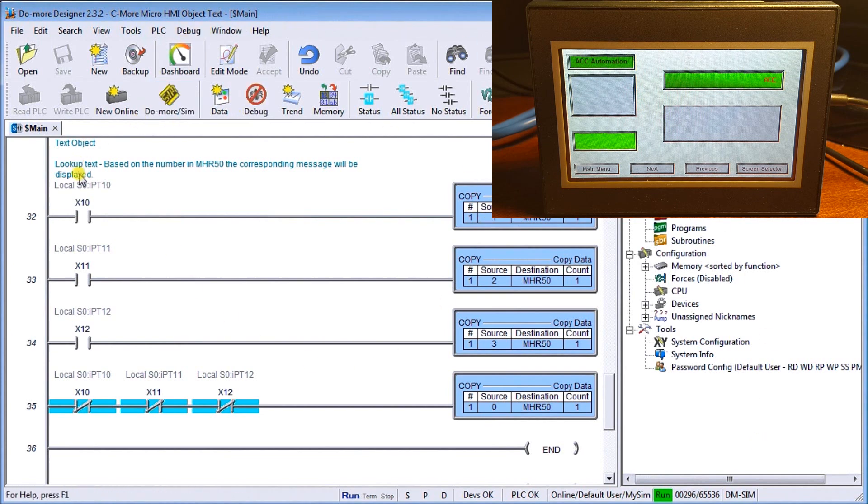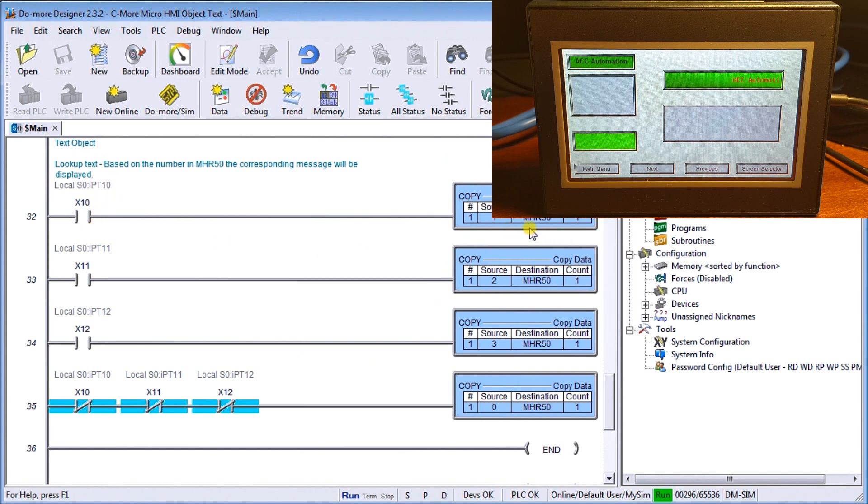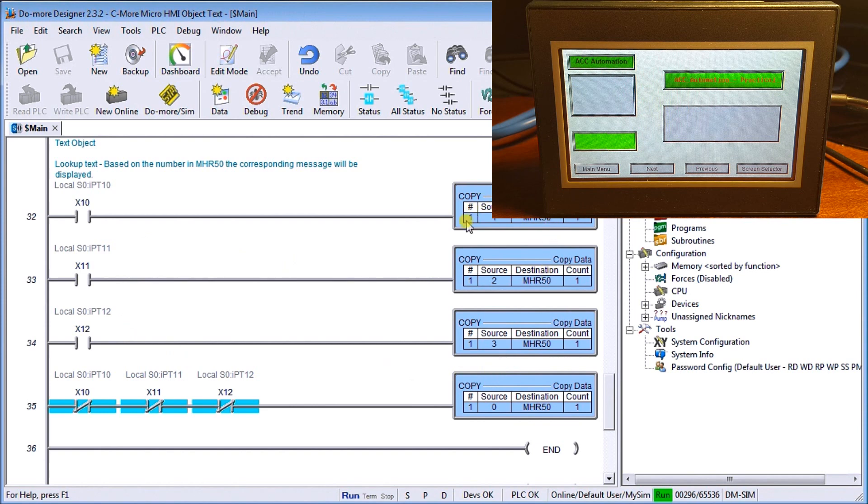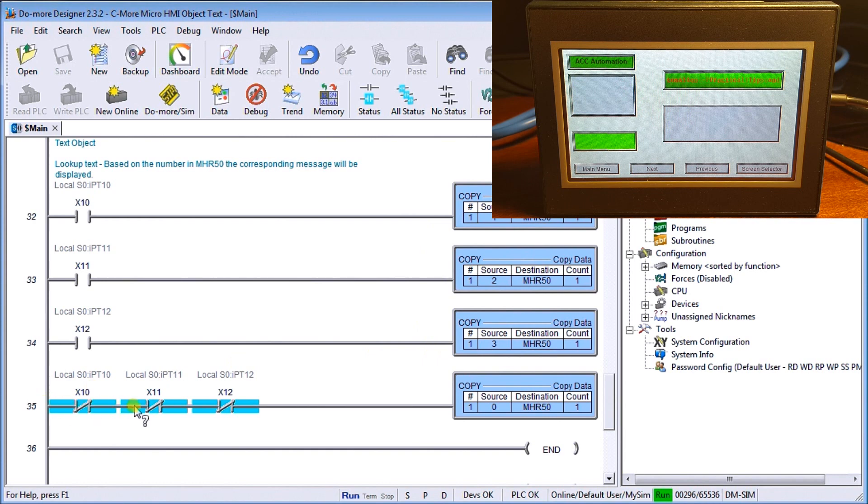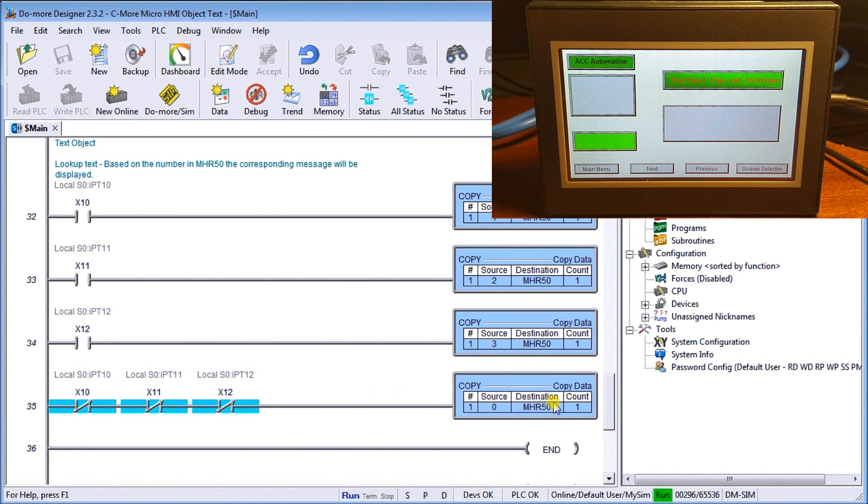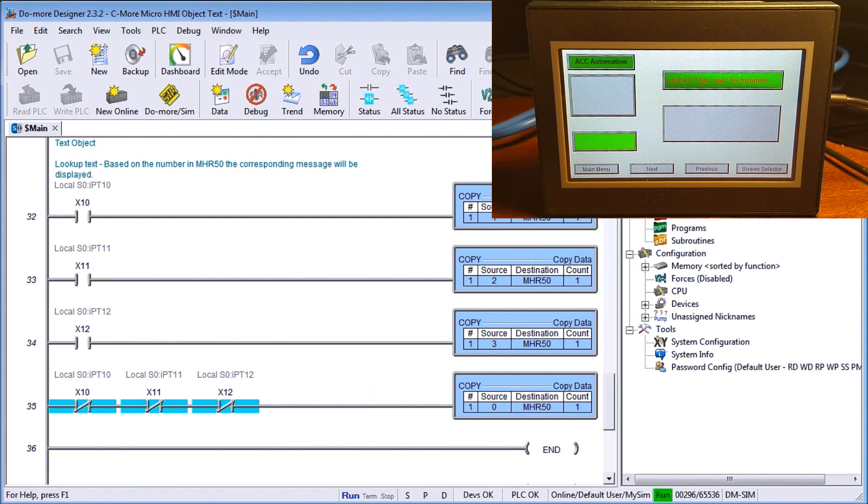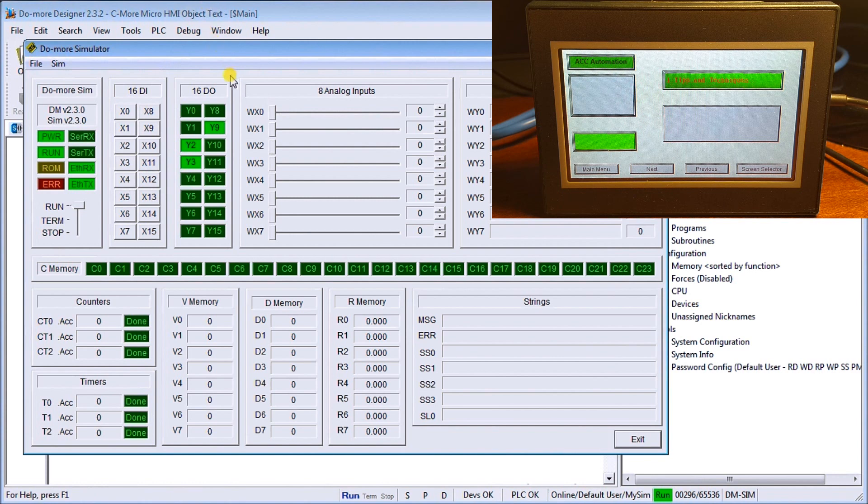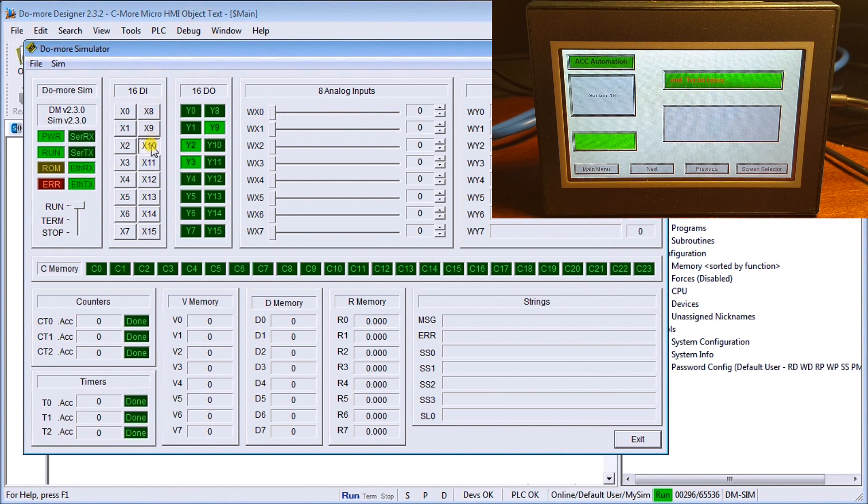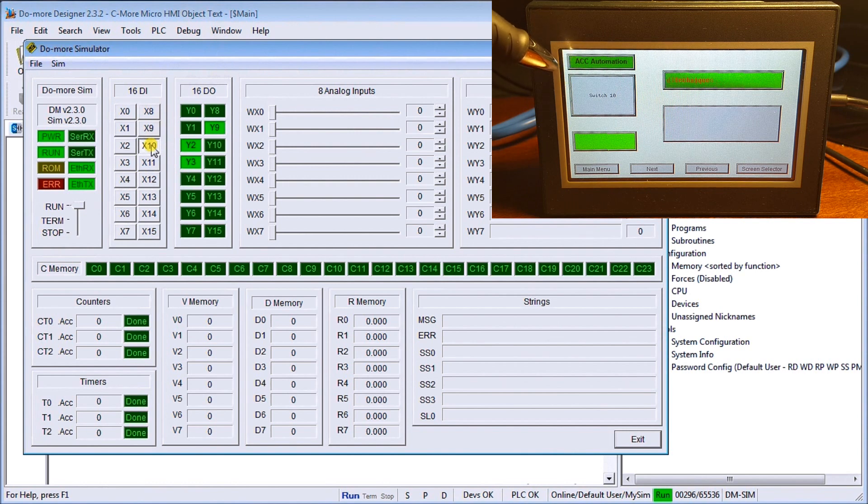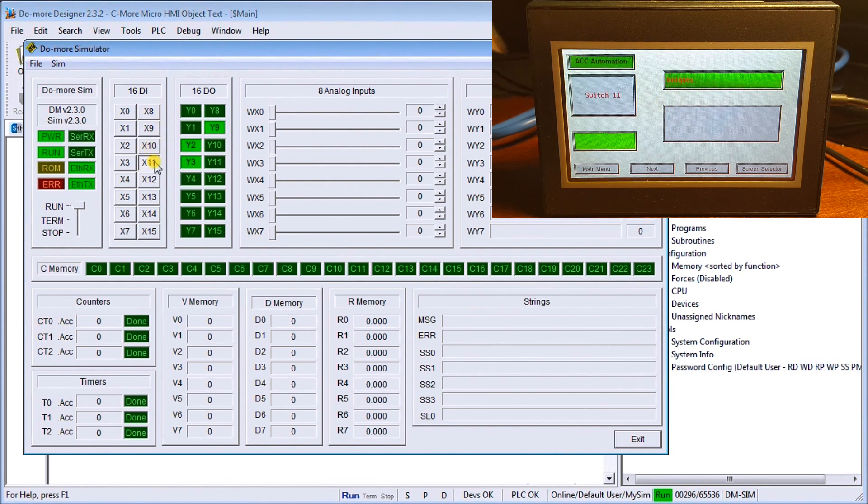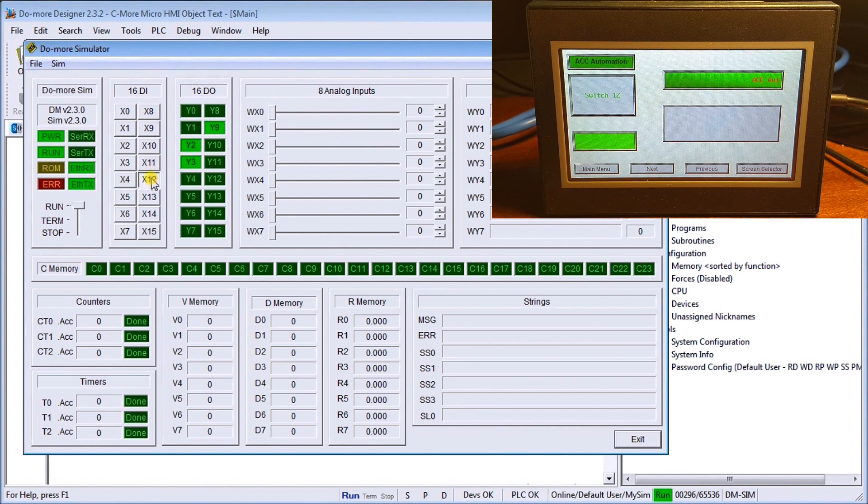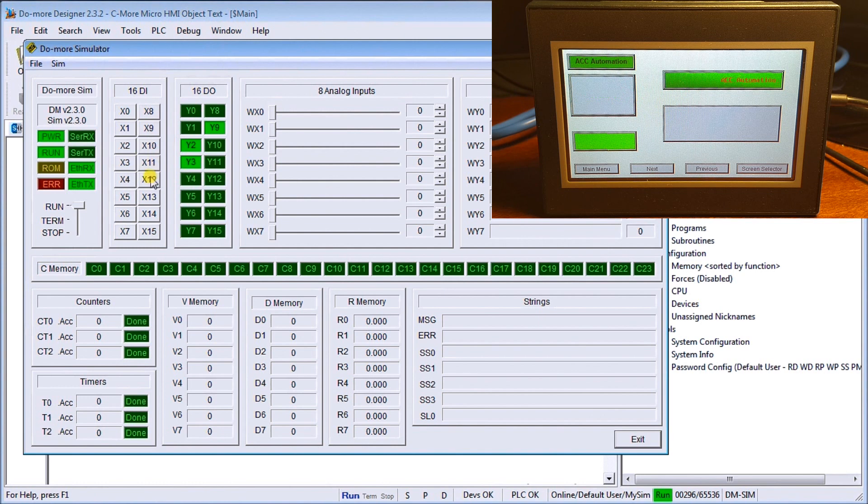If I call up my do more software, I have my text object, my lookup code. If I hit X10, it puts the number one into MHR 50. If I hit X11, it puts 2. X12 will be 3, and there's my three messages that I've pre-programmed. Then if none of those switches are on, then it puts zero into MHR 50, which then resets it. Let's just call up the actual simulator itself. X10, we have it come up switch number 10. Turn that off, switch 11, it actually beeps three times and puts switch 11 on. Turn that off, put switch 12, and it comes up switch number 12 onto my screen. So that's working exactly as we intended it to.